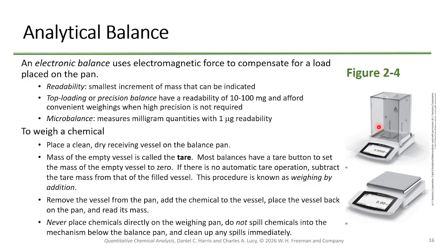So if you can, try to reduce the absolute mass you're measuring. But only to a point, because once you get down low enough, you're going to have errors from the mass being so small. Typically, you want to stay in the 10 gram range. And that's why 25 grams is what we were shooting for in that problem.